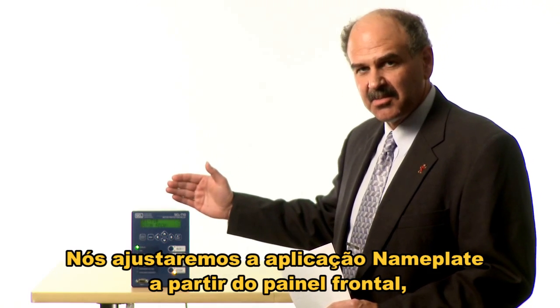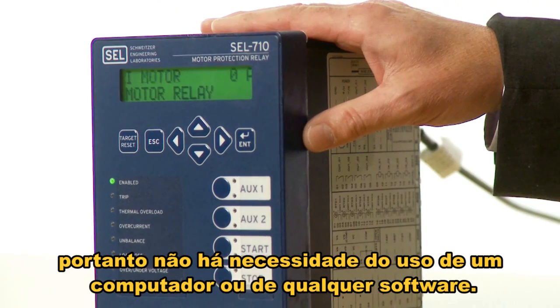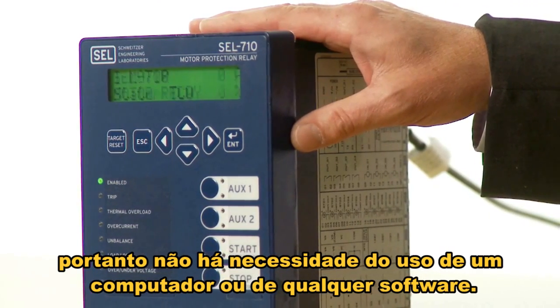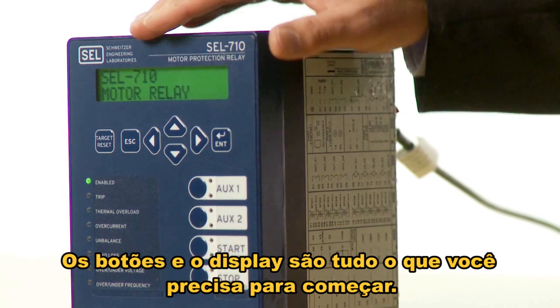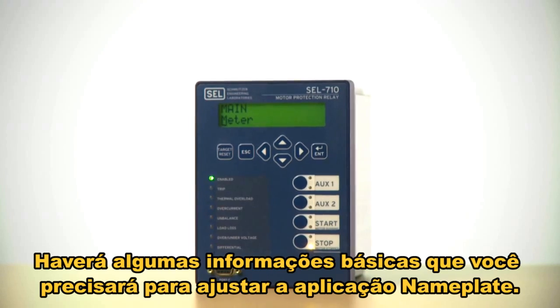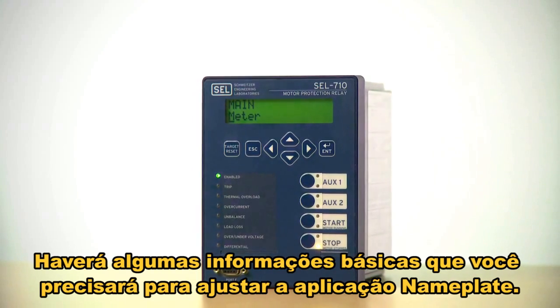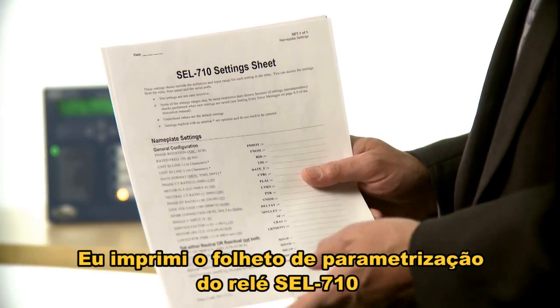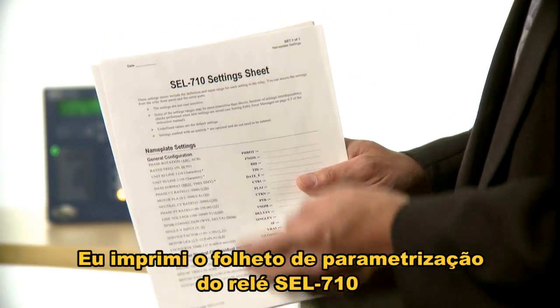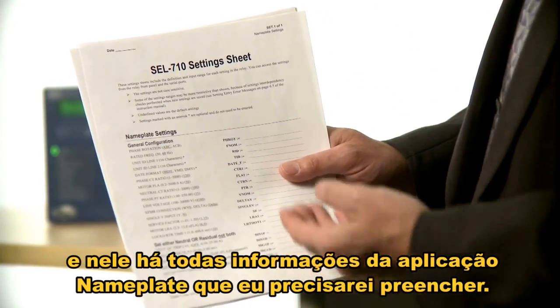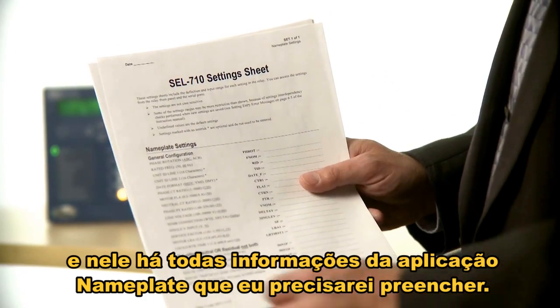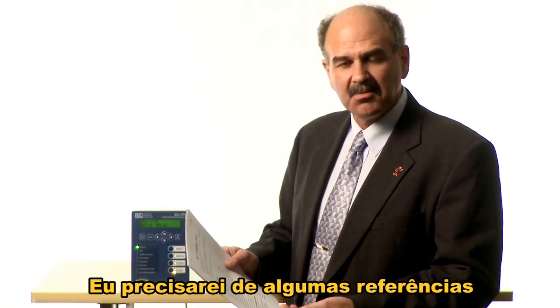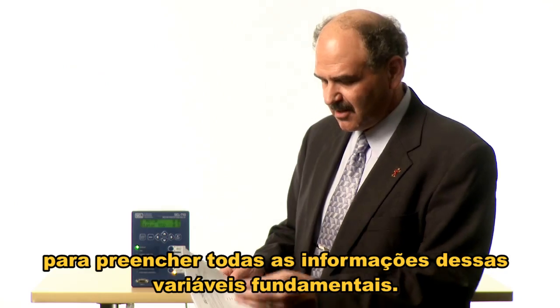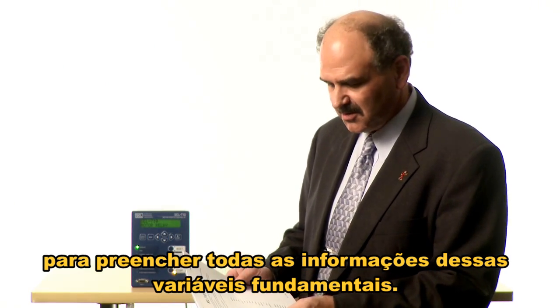We're going to go ahead and set the nameplate from the front panel, so there's no need for a laptop computer or any software. The buttons and the display are all you need to get started. There's going to be some basic information you need to set the nameplate application. Now, I've printed out the SEL-710 settings sheet, and it has all the nameplate information that I'm going to need to fill out. I'm going to need a couple of references to go back and fill in all the information for these key variables.